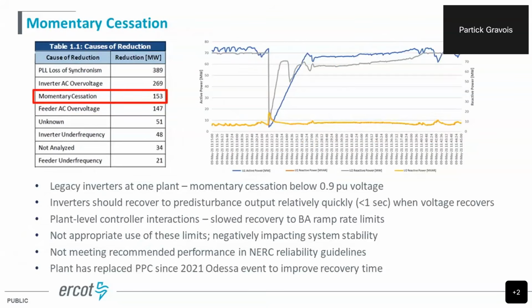The next is a single facility that had momentary cessation. So this is probably the oldest solar facility, transmission level solar facility in ERCOT. This was circa 2015. It came online 2016, but the design was more 2014, 2015. So they have legacy inverters, and it was thought that they really could not disable the momentary cessation, and that was set to go anytime voltage is below 0.9 per unit. They would go into momentary cessation, which means it would current block for all reactive and active power. So this doesn't really meet the requirements, because you're required to provide reactive during the low voltage conditions.